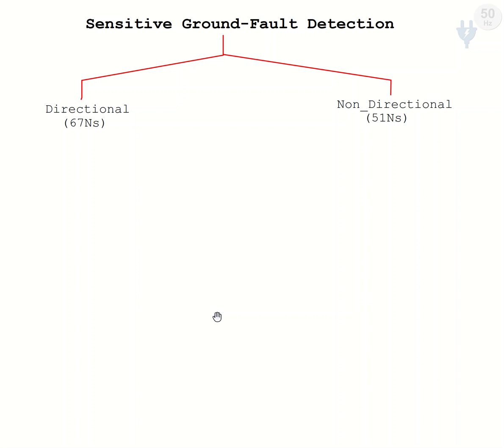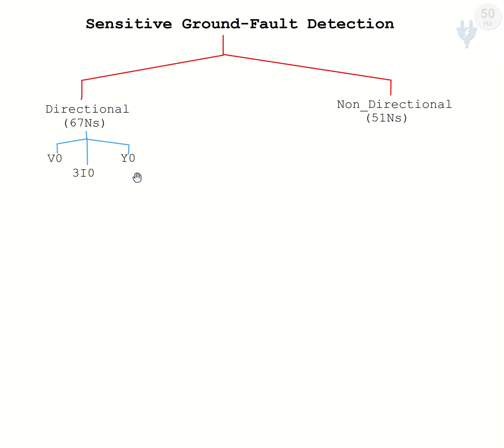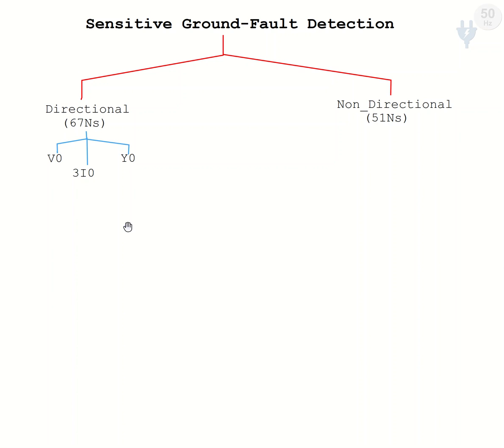For operation of directional sensitive ground fault, we need zero sequence voltage and zero sequence current, or instead of these, we need zero sequence admittance or harmonics of these factors. As the zero sequence voltage harmonic is low and the harmonic of zero sequence admittance is negligible, mostly the harmonics of zero sequence current are used for direction determination.